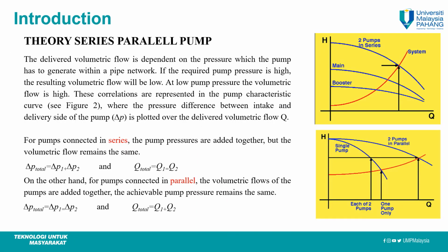When we talk about series and parallel pumps, they have different operations. The amount of volume flow rate increase and the amount of pressure rise or pressure head rise depends on whether the pumps are connected in series or in parallel. In series pump operation, the only essential similarity between the two pumps is that they must be able to operate at the same flow rate. The pumps can deliver totally different levels of pressure as long as they operate at the same capacity. So it is important that the flow rate remains the same.